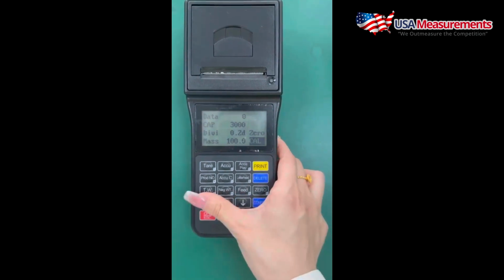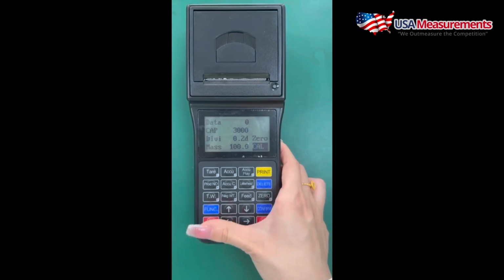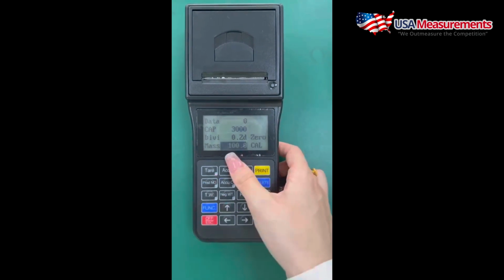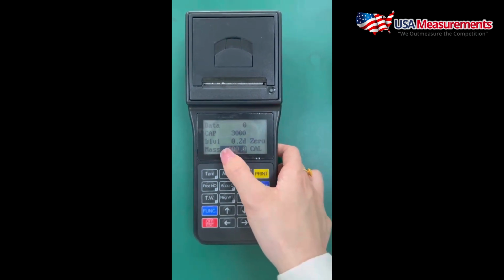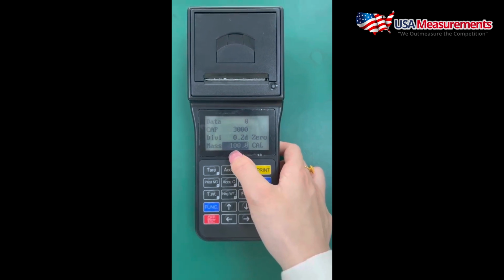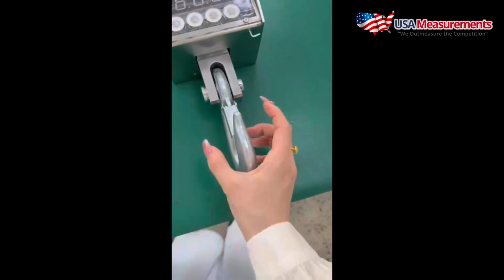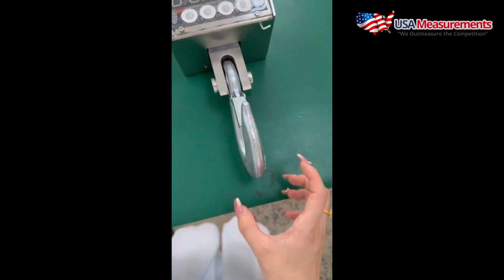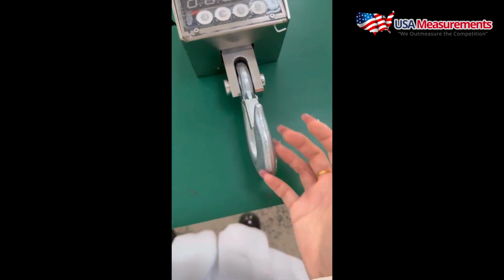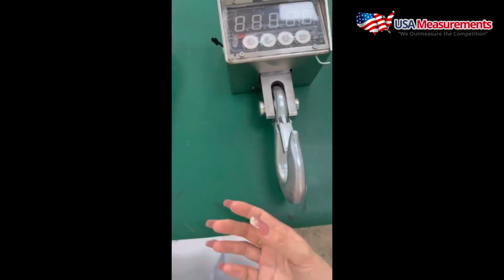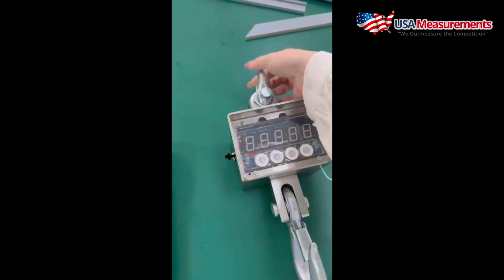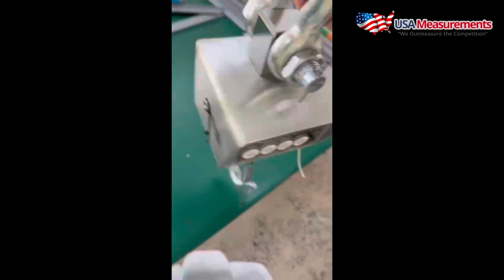Once that's done, we're going to enter our mass. That's our known weight that we'll use to calibrate the scale with. The known weight needs to be in kilograms, so if you have a pound known weight, convert it from pounds to kilograms and enter that as your mass. You need to hang the known weight from the bottom hook.